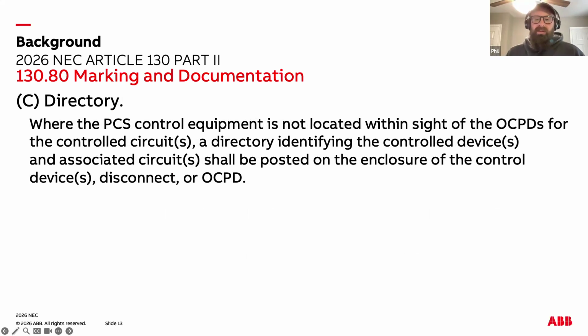When PCS control equipment isn't located where you can see the overcurrent devices it controls, the code requires a directory to be posted so qualified people can easily tell which circuits are being managed. If the PCS controller is not within sight of the OCPDs for the circuits it controls, a directory or listing must be placed on the enclosure of the PCS device, disconnect, or overcurrent protective device. This directory must clearly identify which devices and circuits are being controlled. This ensures that anyone servicing the system immediately understands the relationship between the PCS and the protected circuits.